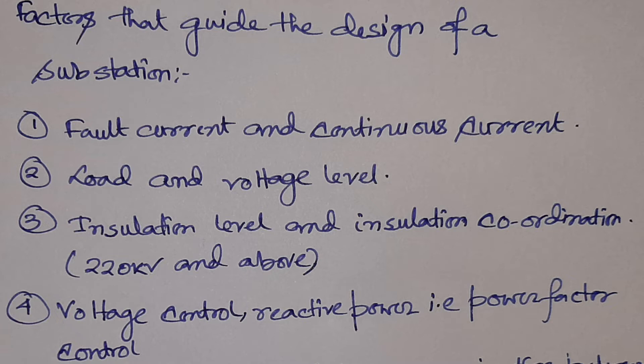There are several factors that guide the design of a substation. Number one is fault current and continuous current — these are two very important parts of a substation design. Then the load and the voltage level: depending on the load you need to select the transformer size, and depending on the power requirements the voltage levels are selected. For example, small-rated motors of rating less than 200 kW will be fed from a lower voltage level.